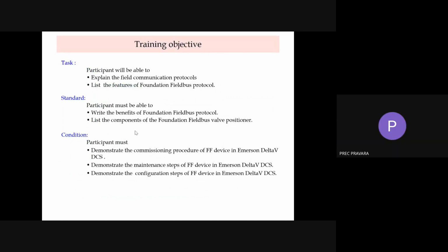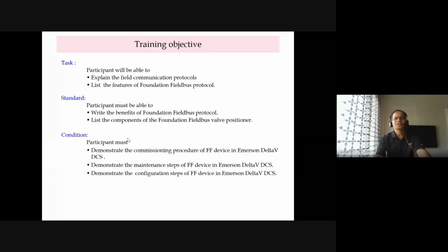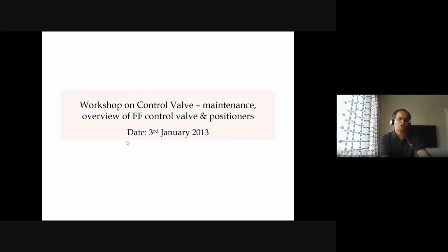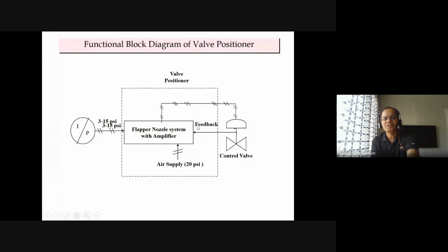Yes, you can start. So yesterday we were discussing control positioners, and there are three generations we have seen: pneumatic, then analog, 4 to 20 milliamp meaning HART, foundation meaning field bus, and now control valves are also available on wireless.